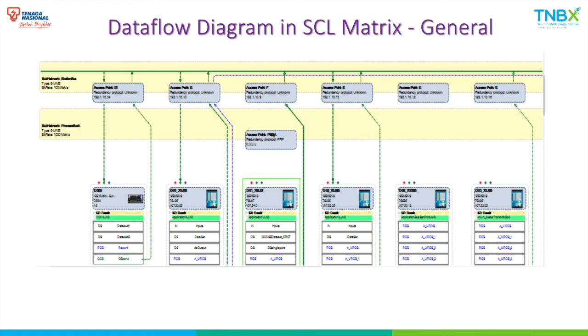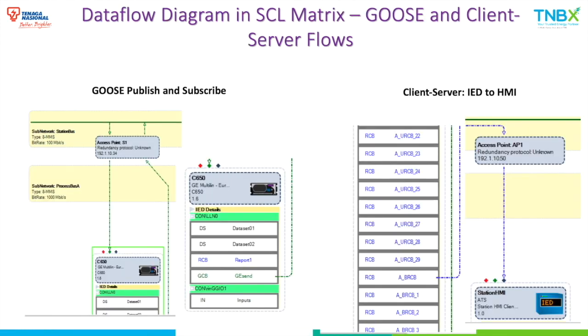So just a snapshot of the engineering flow—this is the final result when we completed the engineering process. This is in SCL Matrix, the SCT tool. This is called the data flow diagram, where you can see the IEDs connected to a subnet and conducting information exchange between them. We configured GOOSE publication and subscription, as well as client-server communication from a certain report control block to the station HMI.